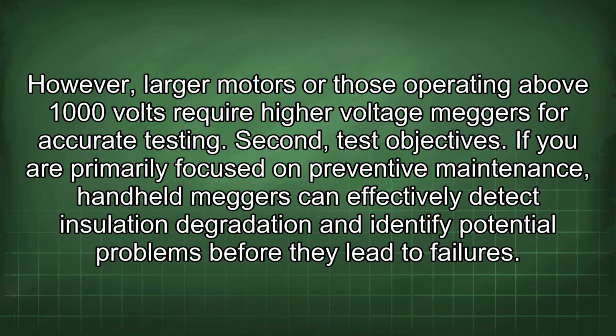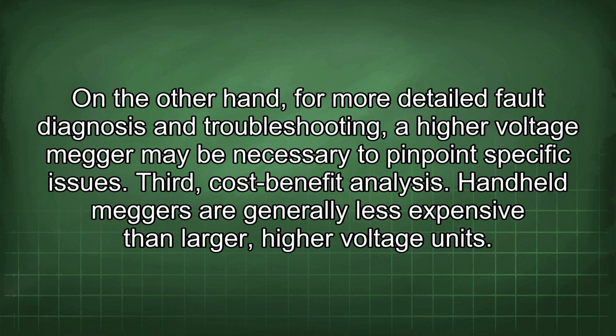Second, test objectives. If you are primarily focused on preventive maintenance, handheld Meggers can effectively detect insulation degradation and identify potential problems before they lead to failures. On the other hand, for more detailed fault diagnosis and troubleshooting, a higher voltage Megger may be necessary to pinpoint specific issues. Third, cost-benefit analysis.